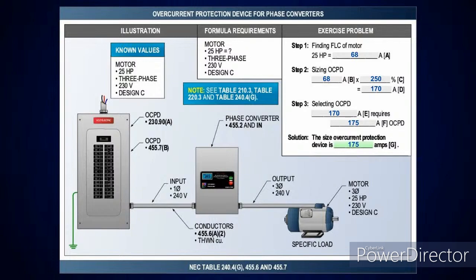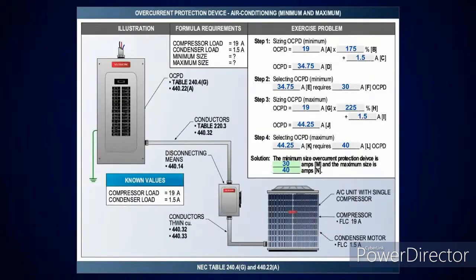So that is the rule of thumb I want you to remember. 125% or less, go up to the next standard size. 250% or more, or over 125%, drop down to the next standard size. The only two times you want to look at this differently are in transformers and here at phase converters. Okay. Now, the next one's AC units.